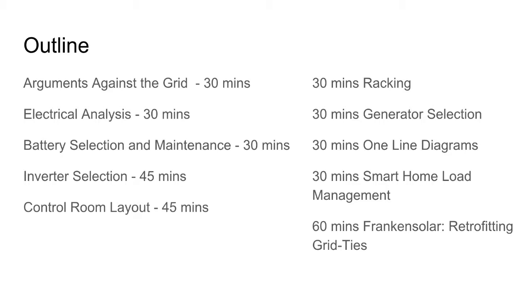In Mississippi, where I'm located, we get very tall trees. And solar is not supposed to go in the shade, but partial shade conditions are okay. But if you have any amount of shade on your rooftop, module level panel electronics are generally how you want to go. And I've developed an installation technique that really alleviates a lot of my concern about, well, you're increasing your labor and you're increasing your wiring, and that's going to cause failure, and you're inviting more damage because of squirrels and other pests living on your roof getting into the wires. We'll spend a little bit of time talking about that.